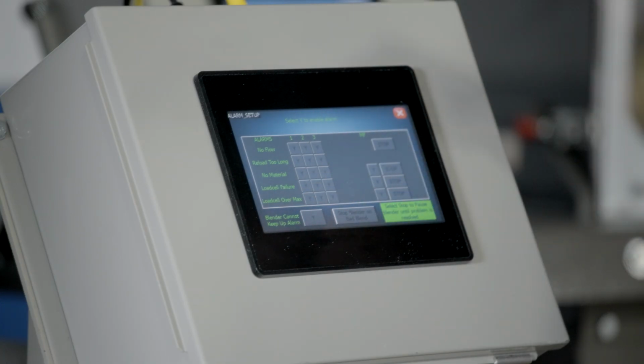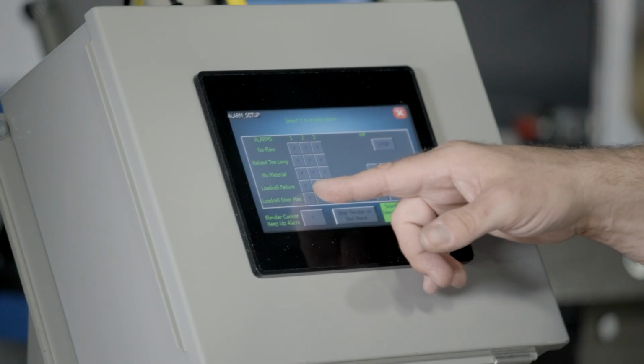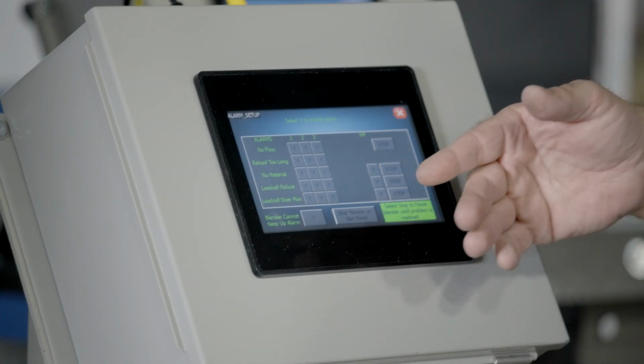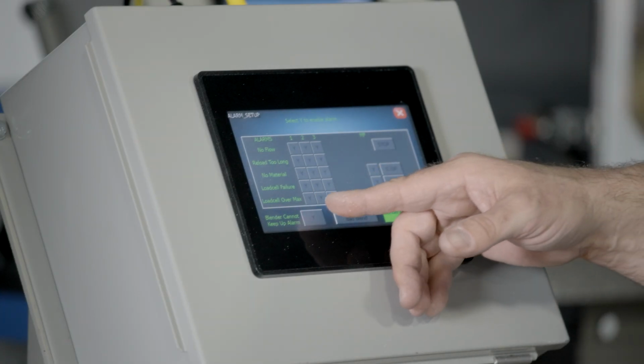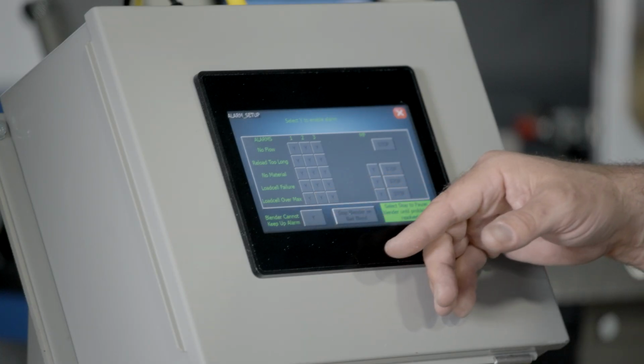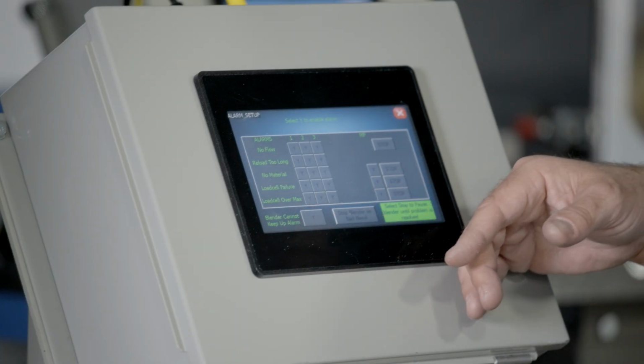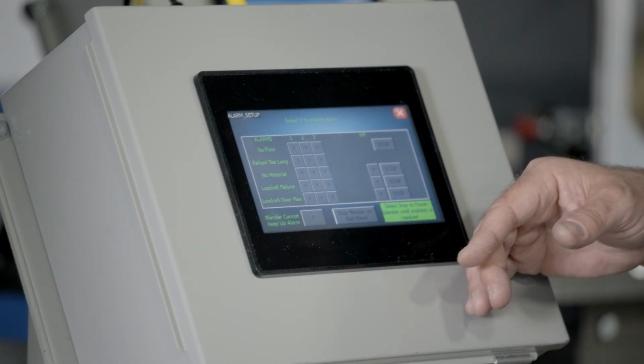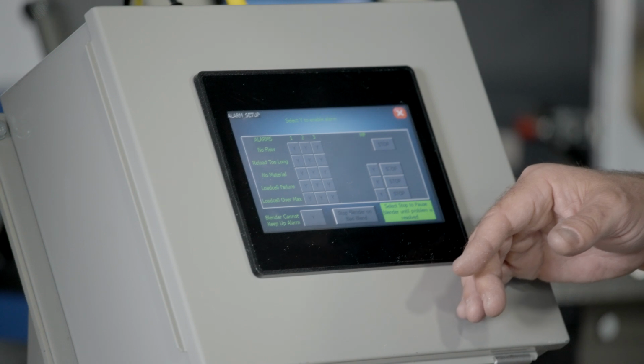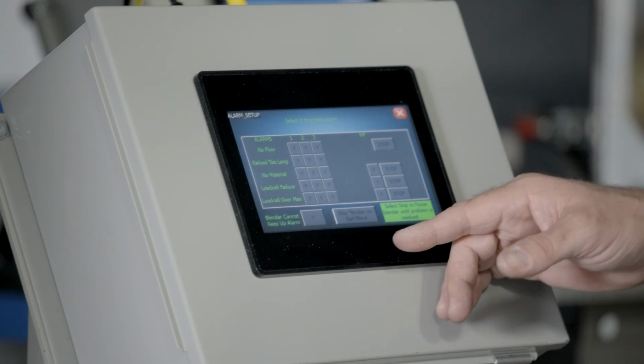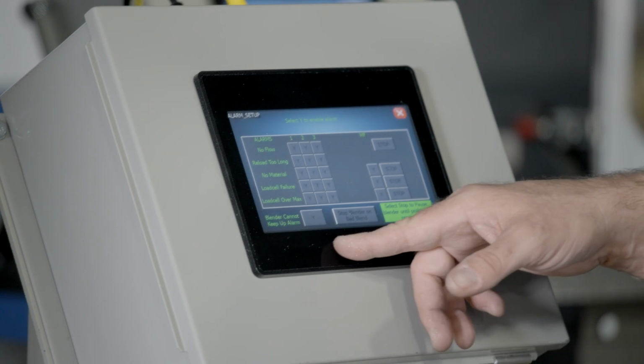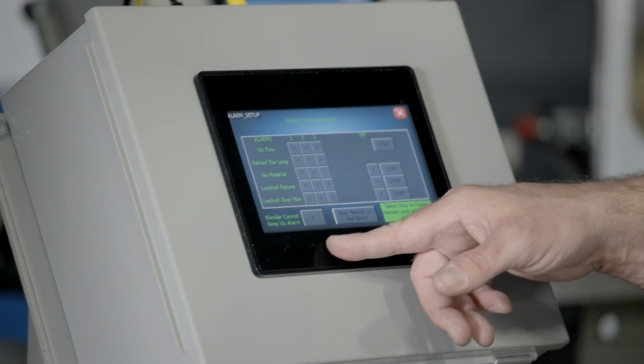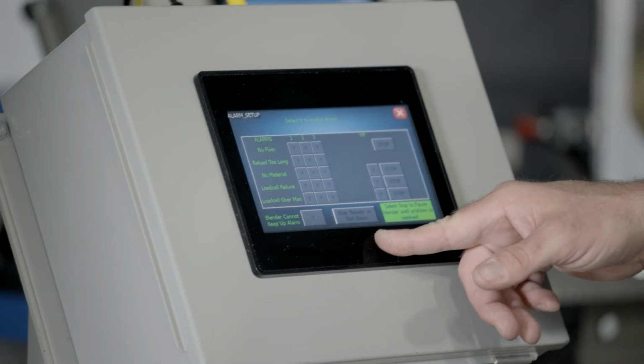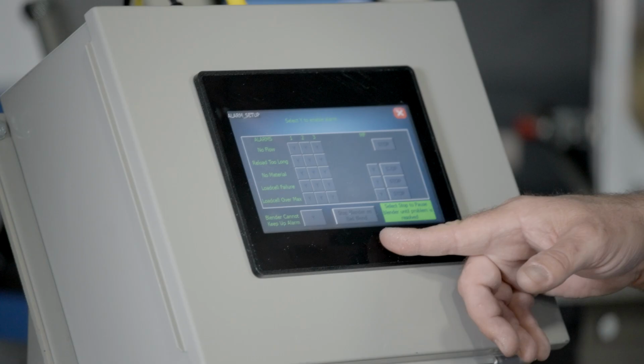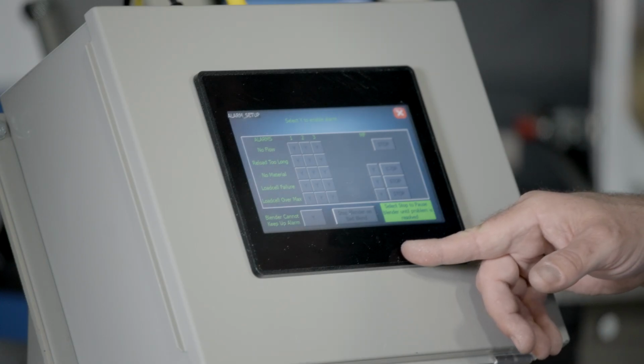No material is when we're completely empty. Load cell failure is when we're not seeing the proper readings from the load cell. And load cell over max is if for some reason the load cell is overloaded, so if maybe somebody put their hand on it or set something on the weigh hopper. And also we have blender cannot keep up, and we have stop blender on bad blend. If we can't make the proper blend, it'll make the blender stop.